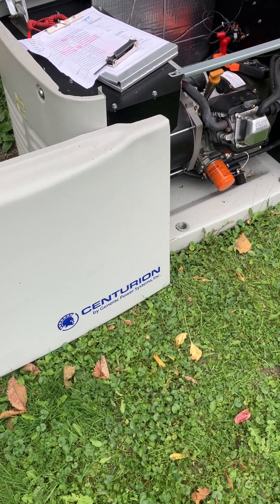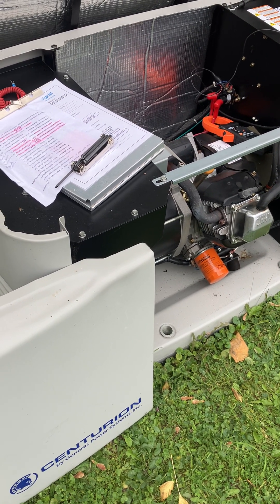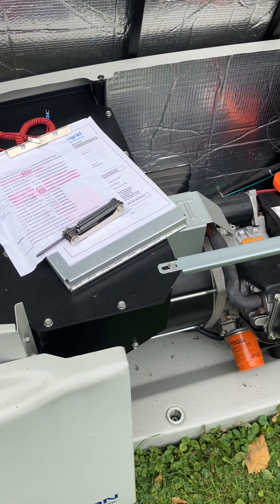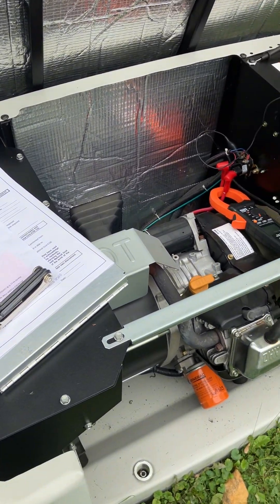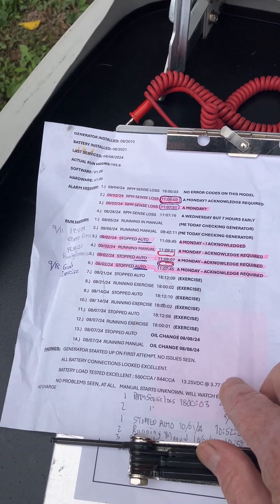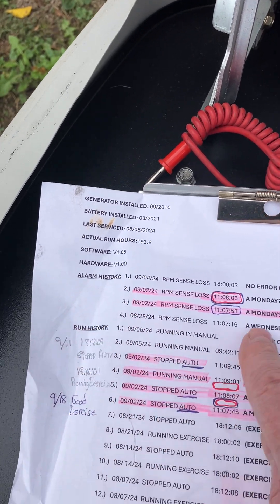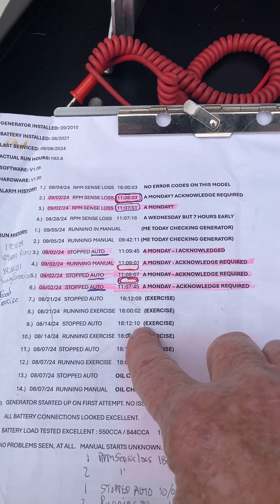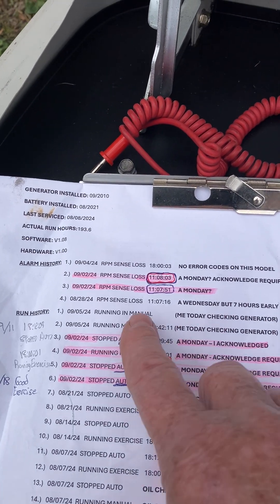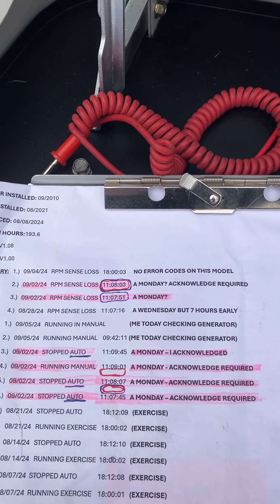I'm redoing this — I did a video just the other day on an RPM sense loss, one I'd never seen before. I went to the unit, got the run history and the alarm history, and it was working fine right up until it started getting the RPM sense loss.